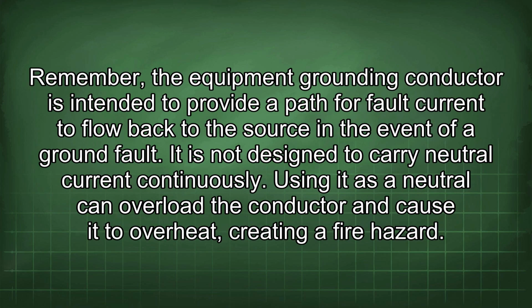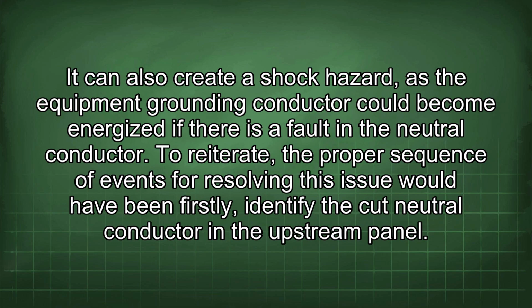Remember, the equipment grounding conductor is intended to provide a path for fault current to flow back to the source in the event of a ground fault. It is not designed to carry neutral current continuously. Using it as a neutral can overload the conductor and cause it to overheat, creating a fire hazard. It can also create a shock hazard, as the equipment grounding conductor could become energized if there is a fault in the neutral conductor.